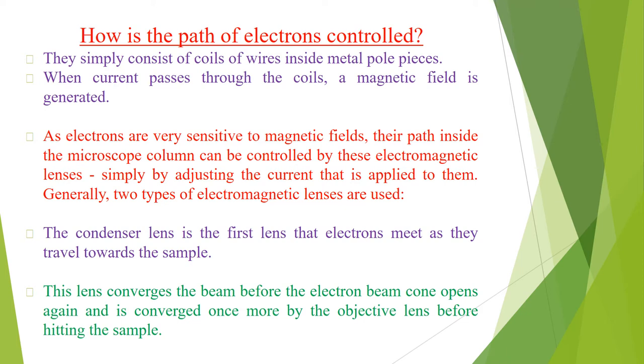Here we will discuss how the path of electrons is controlled. In a similar way to optical microscopes, lenses are used to control the path of the electrons. Because electrons cannot pass through glass, the lenses used here are electromagnetic — they simply consist of a coil of wires inside metal pole pieces. When current passes through the coils, a magnetic field is generated. Electrons are very sensitive to magnetic fields and their path inside the microscope column can be controlled by these electromagnetic lenses.